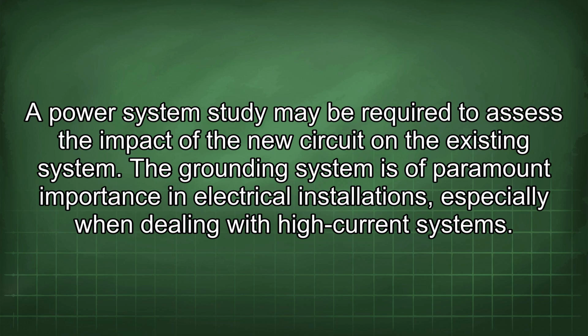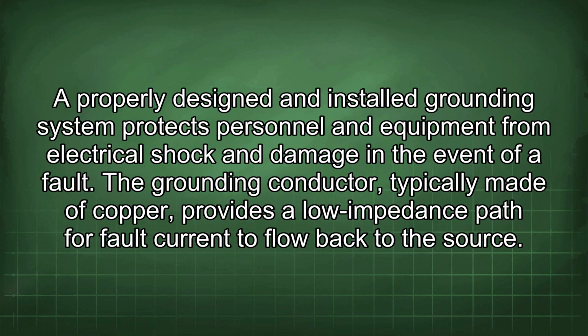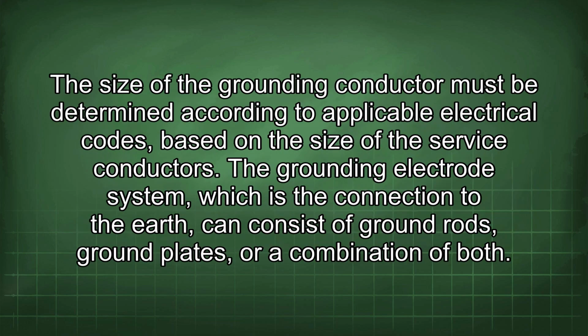The grounding system is of paramount importance in electrical installations, especially when dealing with high current systems. A properly designed and installed grounding system protects personnel and equipment from electrical shock and damage in the event of a fault. The grounding conductor, typically made of copper, provides a low impedance path for fault current to flow back to the source. The size of the grounding conductor must be determined according to applicable electrical codes based on the size of the service conductors.